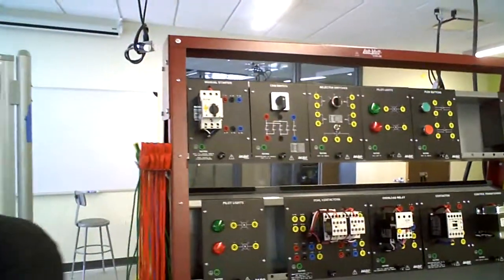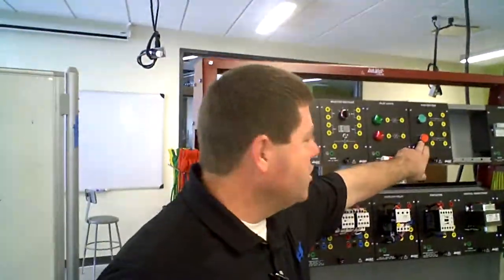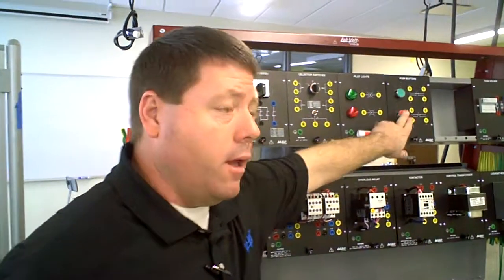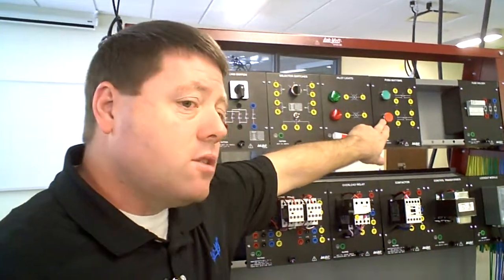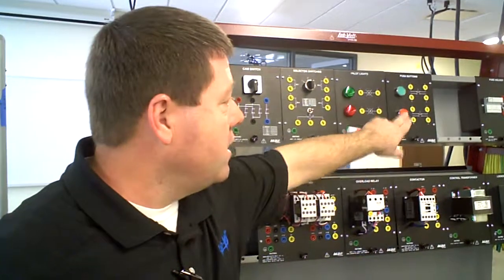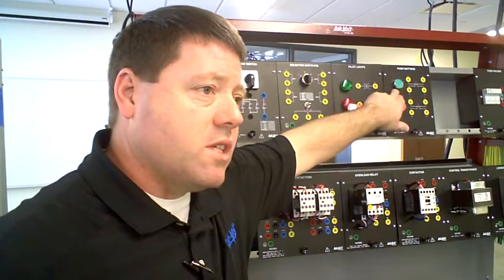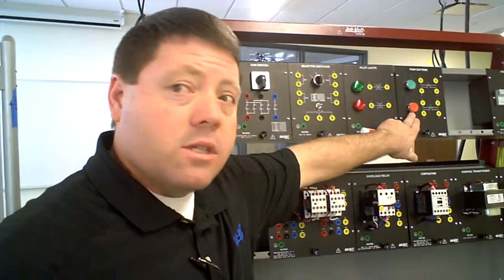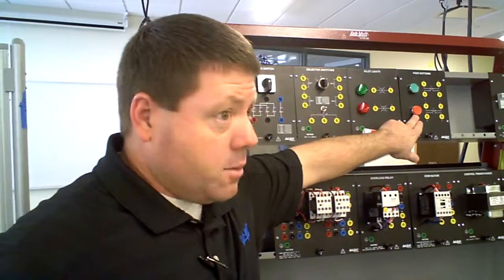Is if something happens, you may not be able to press this, which most of your stop buttons are now. Do you call that a second stop? Yes. This is not considered an E-stop. This is just a stop. Second stop. And most of your new buttons now have the stop button extended. You don't see the red buttons recessed like the green buttons are anymore. Because people used to use these as E-stops.